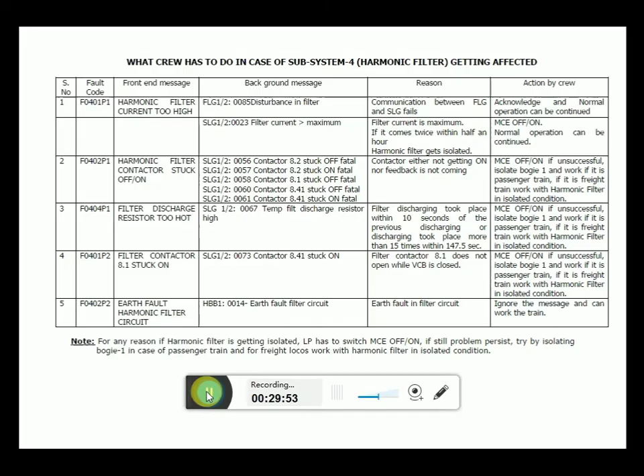So harmonic filter isolated in case of empty stock or coaching trains, we can isolate SR1 and switch off MCE and switch on MCE. If harmonic filter comes into service, we can work with normal speed. For any reason, if you want to isolate the harmonic filter, this MCB 127.2/1, monitoring MCBs for harmonic filter and HB1 breakers. We have to trip this MCB 127.2/1 with precautions, and we have to close the harmonic filter cock available on the pneumatic panel. Then only we can isolate the harmonic filter. Once the harmonic filter is isolated, we can work with 40 kmph. After reaching 40 kmph, TE will become 0.